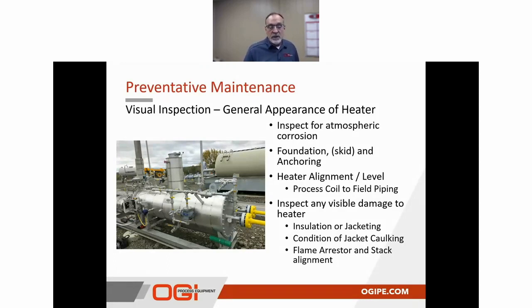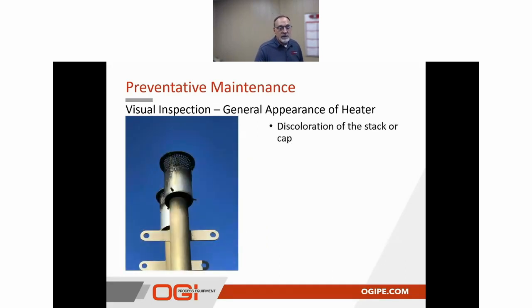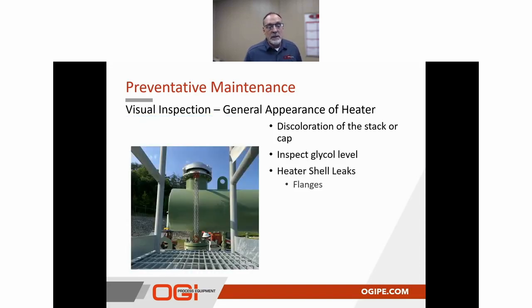And then checking the alignment of the flame arrestor and the stack to ensure that they're plumb. Next, we're going to look at the stack itself and confirm whether it is normal. In this case, as you can see, we have a discolored stack, identifying something potentially wrong with the combustion or the system itself. We'll also inspect the heater shell for leaks, and we want to know about the glycol level. Is it appropriate, and is it showing in the expansion tank?